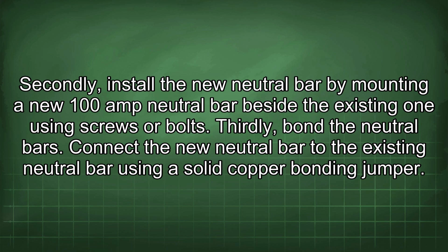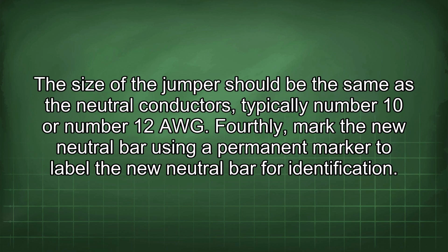Thirdly, bond the neutral bars. Connect the new neutral bar to the existing neutral bar using a solid copper bonding jumper. The size of the jumper should be the same as the neutral conductors, typically number 10 or number 12 AWG. Fourthly, mark the new neutral bar using a permanent marker to label the new neutral bar for identification.